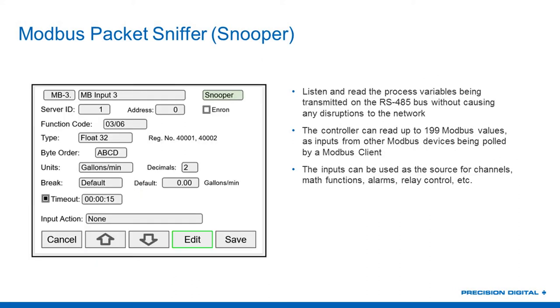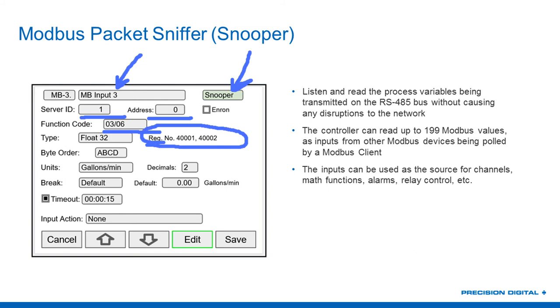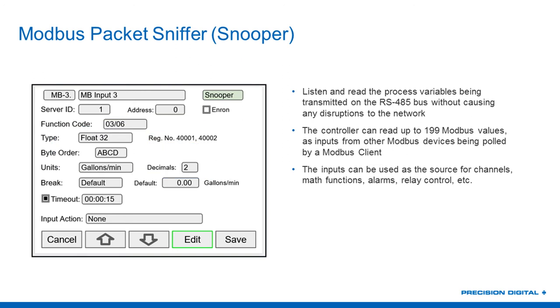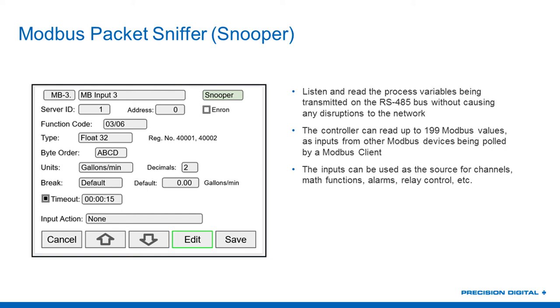How do you program snooper mode? Much like client mode — you give it a name, set it up for snooper mode input, give it the Modbus ID of the device you want to listen to responses from, give it the function code and register address. Just like before, it's a lookup on the device. In this case, whenever it hears Modbus address device 1 respond with register number 40,001, it knows that's what it's looking for — it didn't request that information, some other master did, but that's what it wants to treat as an input.